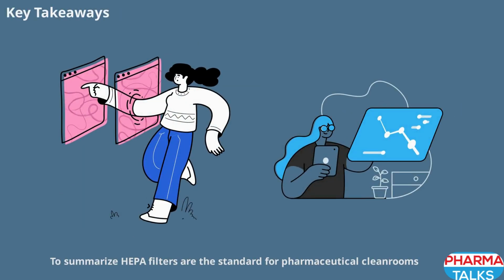Summarize: HEPA filters are the standard for pharmaceutical cleanrooms, offering a balance of efficiency, cost, and regulatory compliance. ULPA filters are reserved for situations where extreme cleanliness is required, but they come with higher costs and operational challenges. Ultimately, compliance with standards and regulations is more important than simply choosing the highest efficiency filter. Proper selection, installation, validation, and ongoing monitoring are the keys to maintaining a safe and effective cleanroom environment.